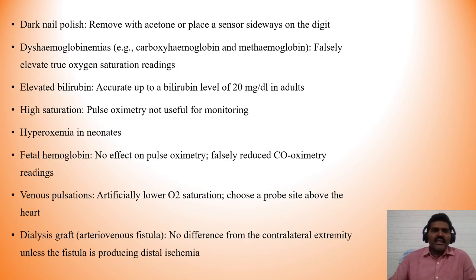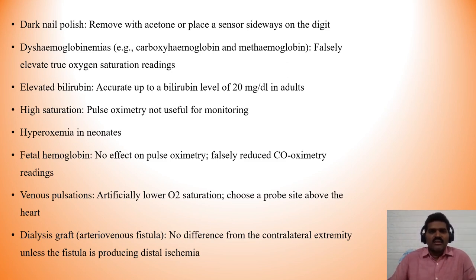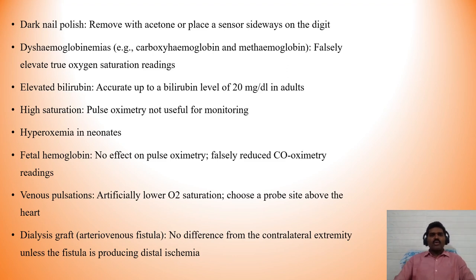Dark nail polish should be removed with nail polish remover, or the sensor placed sideways on the digit so light traverses the pulp. Dyshemoglobinemias — specifically carboxyhemoglobin and methemoglobin — can cause falsely elevated true oxygen saturation readings. Elevated bilirubin: readings are accurate up to a bilirubin level of approximately 20 mg/dL. At high oxygen tensions, pulse oximetry is not useful for monitoring hyperoxemia. Fetal hemoglobin has no direct effect on pulse oximetry, but can cause falsely reduced co-oximetry readings. Venous pulsations can artificially lower SpO2 — choose a probe site above the level of the heart. Dialysis grafts with an arteriovenous fistula show no difference from the contralateral extremity unless the fistula is producing distal ischemia.